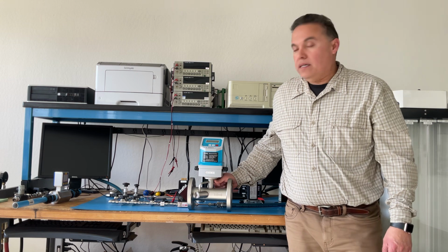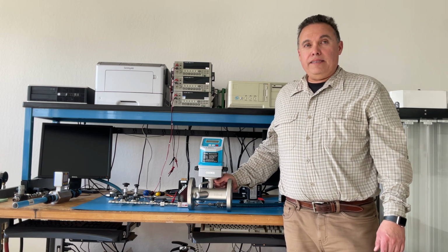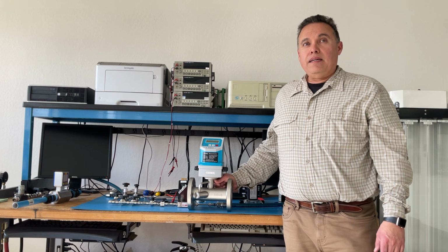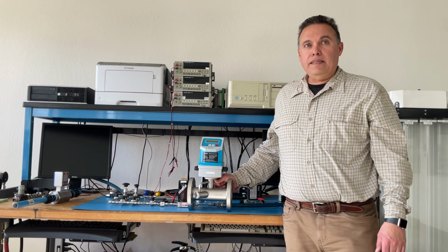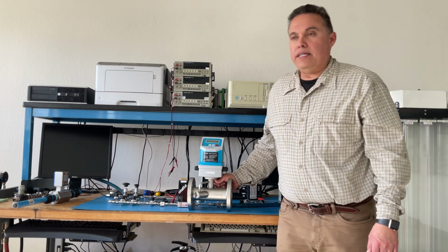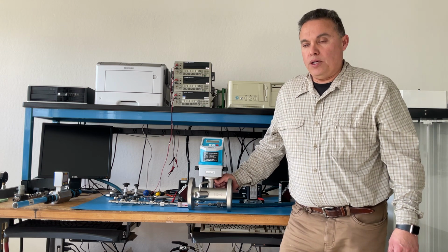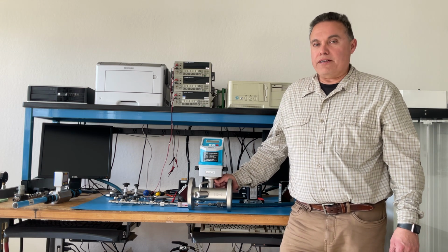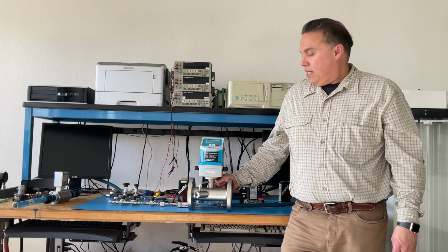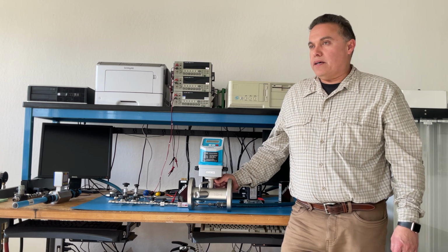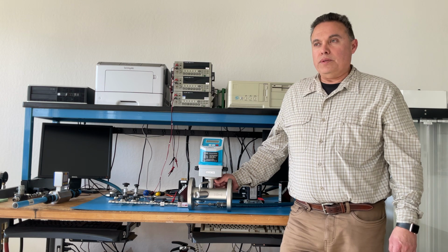Sweet. So it sounds to me like one of the things that's different about Tactical Flow Meter is they use a different calibration process. Do you want to talk about how Tactical Flow Meter does that versus some of the other flow meters out there? Sure. First of all, we use NIST traceable flow standards, and these flow standards are very high accuracy, many times higher than the accuracy of the device under test. This particular meter and all of our meters, we have a special way of characterizing the sensor response. We'll do a characterization of the meter.